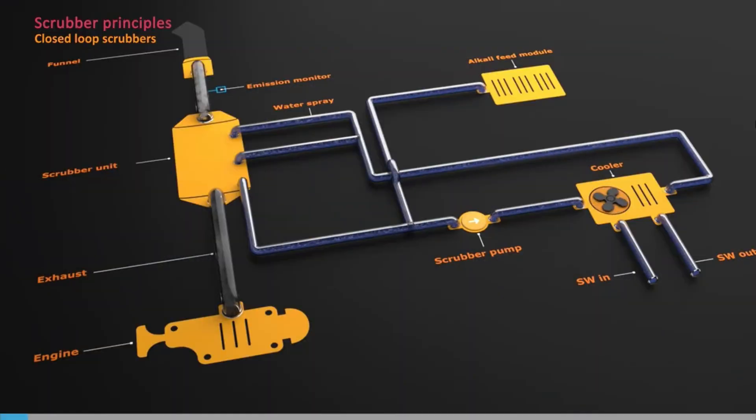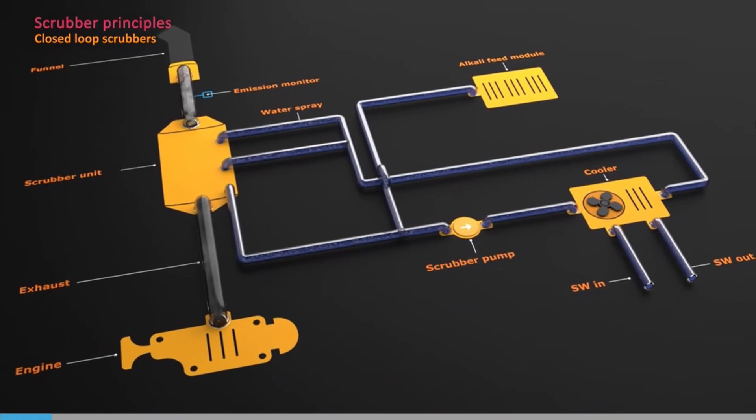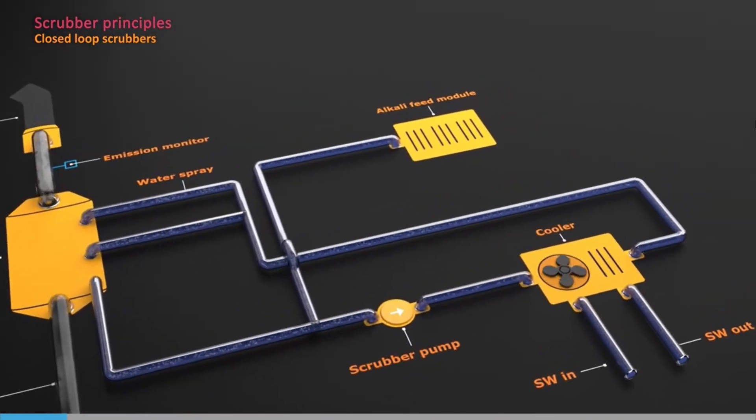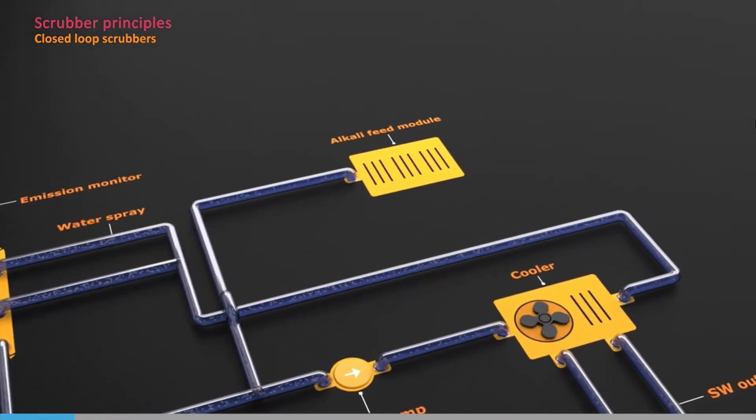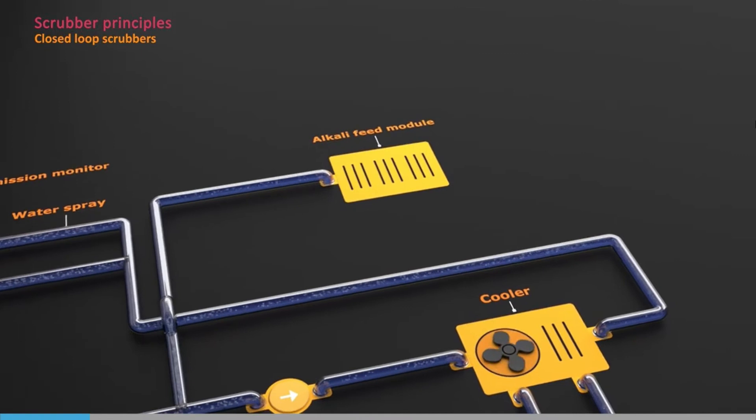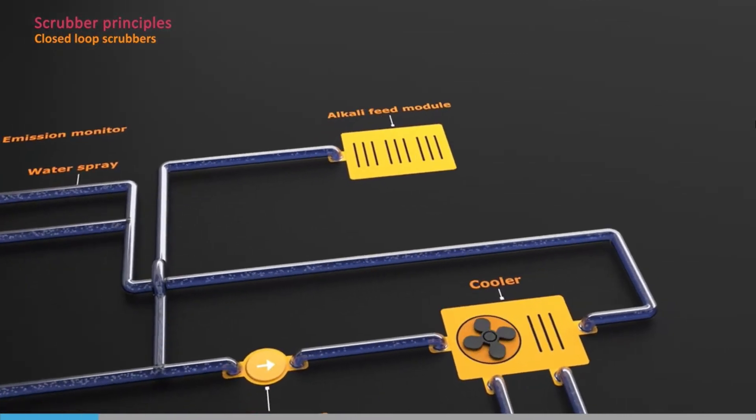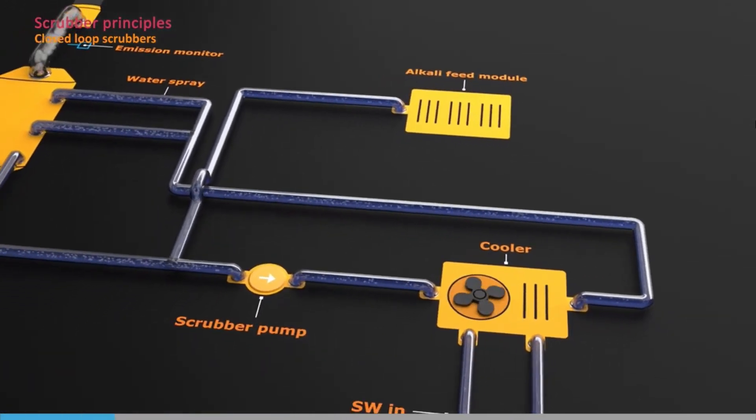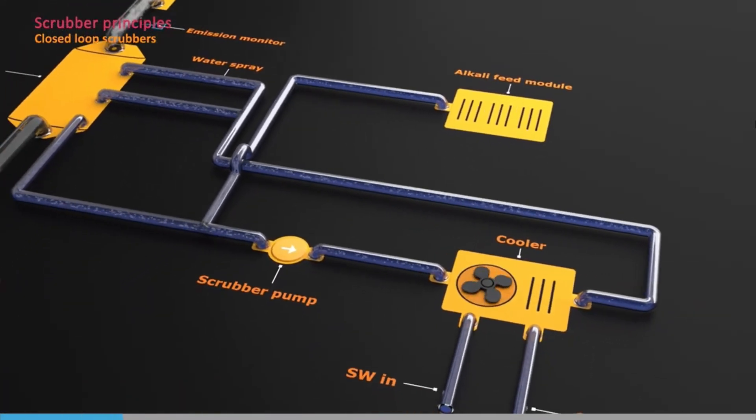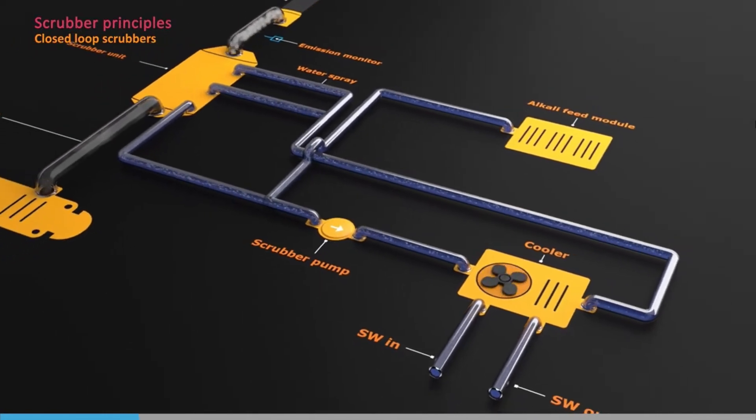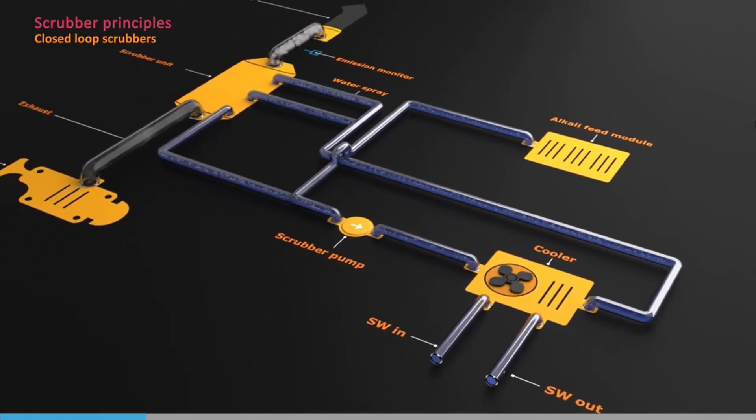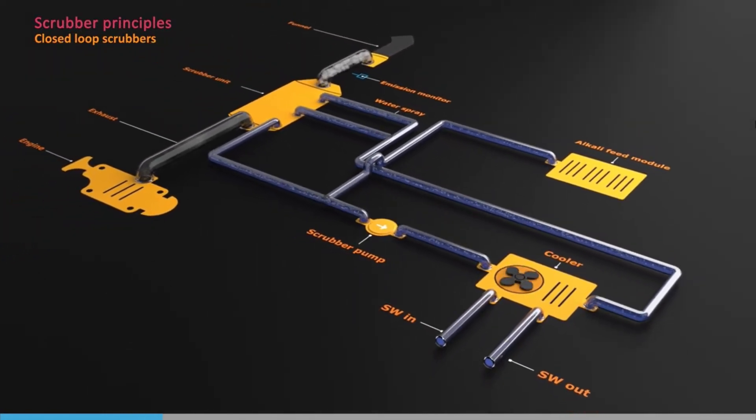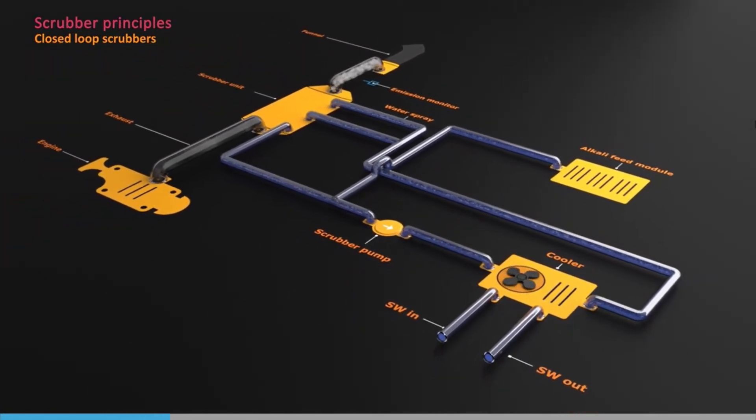Closed-loop scrubbers are used to avoid the discharge of acidic products into the sea. Most use fresh water, with the addition of an alkali, usually caustic soda or magnesium oxide, to wash out the sulphur oxides. Since the system is a closed-loop, the circulating water needs to be cooled.